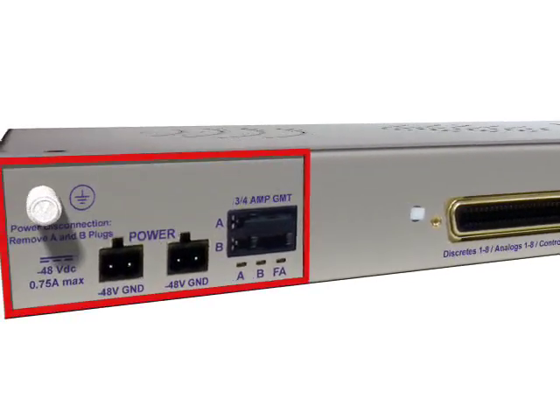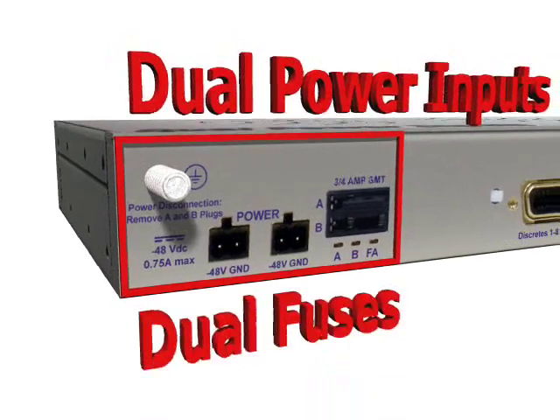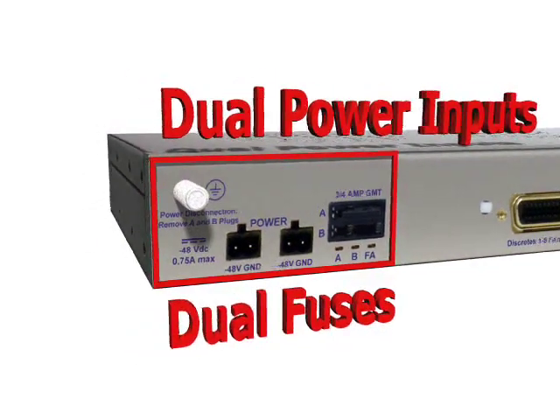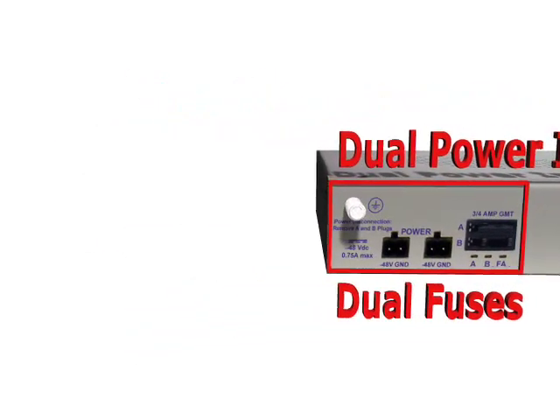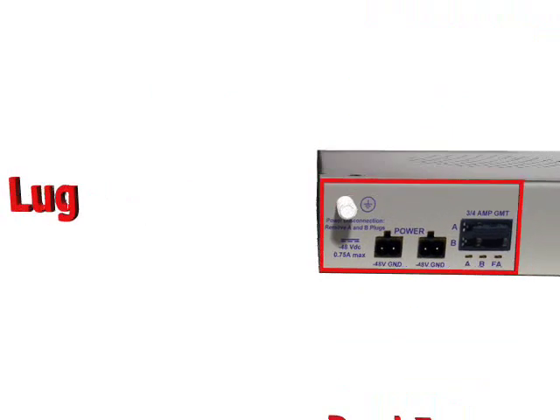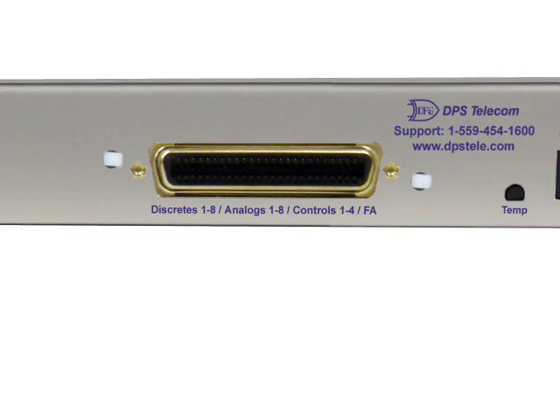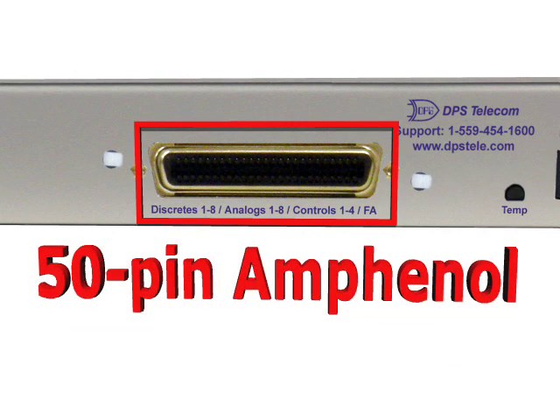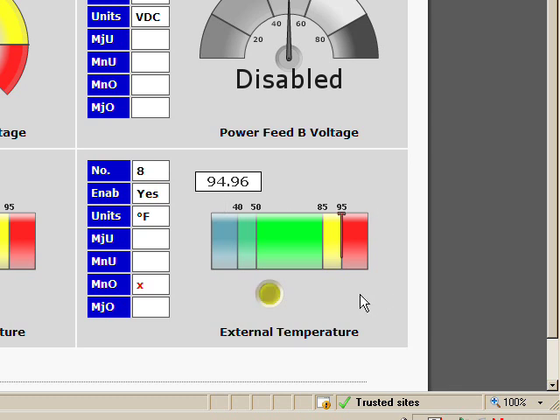Starting from the left side, you'll see dual power inputs, dual fuses to go along with them, and, to dissipate electromagnetic interference, a grounding lug. There's also an industry standard 50-pin Amphenol connector. This provides an interface for the SCADA-Guardian's 8 discrete inputs, 4 control relays, and 8 analog inputs. Those 8 analog inputs allow you to take in detailed analog sensor data from your analog sensors like temperature, humidity, flow rates, and other important factors.